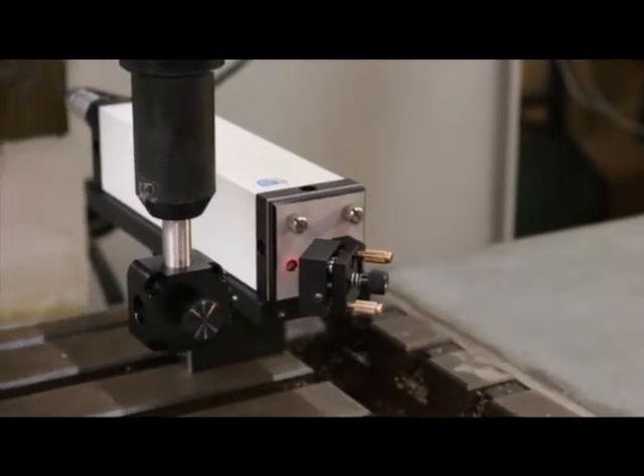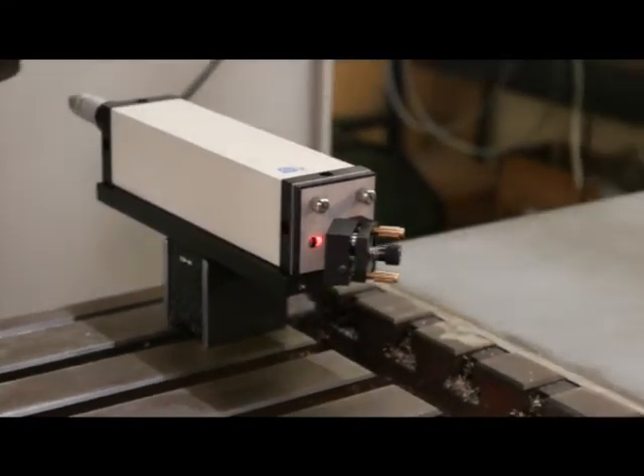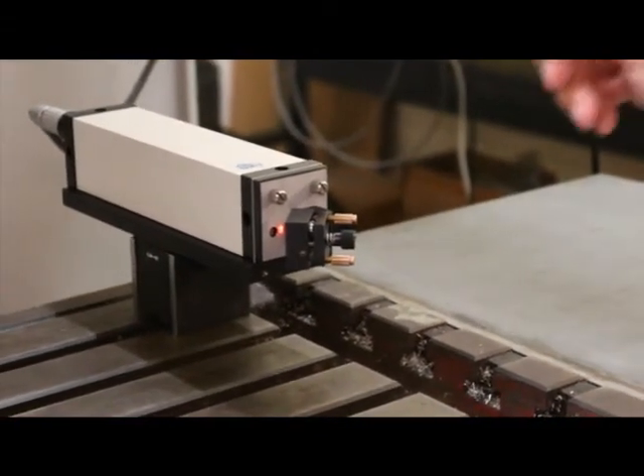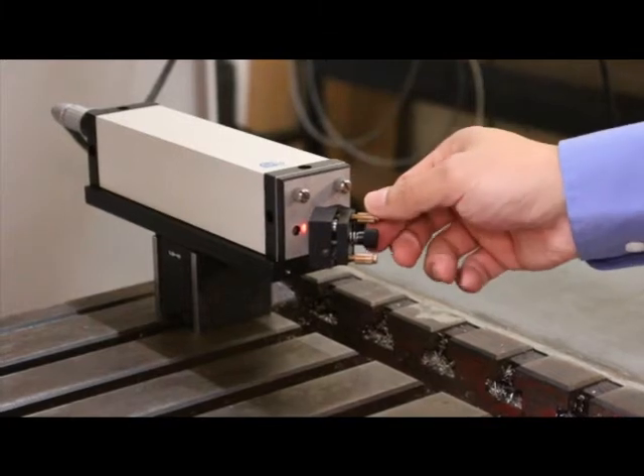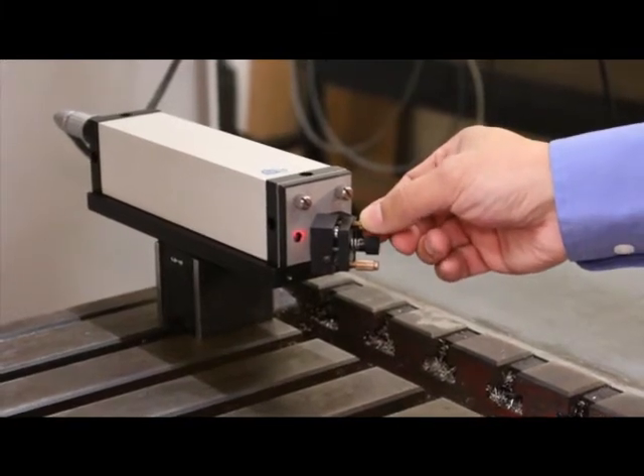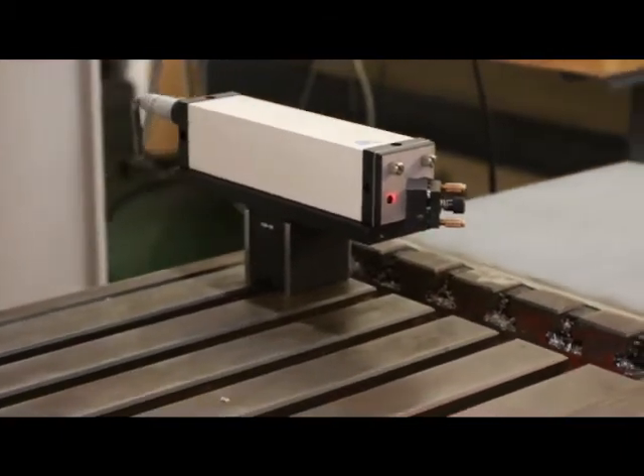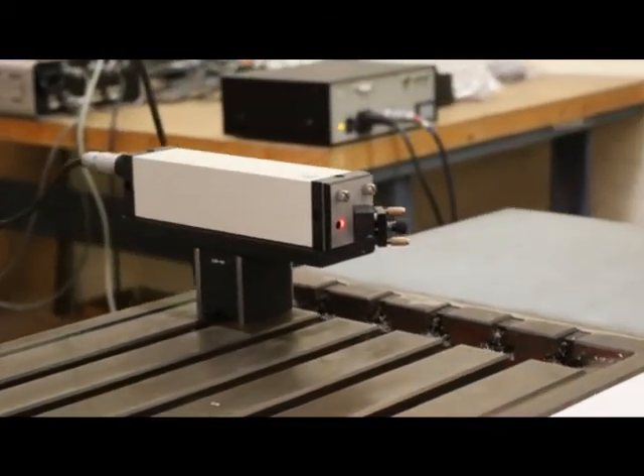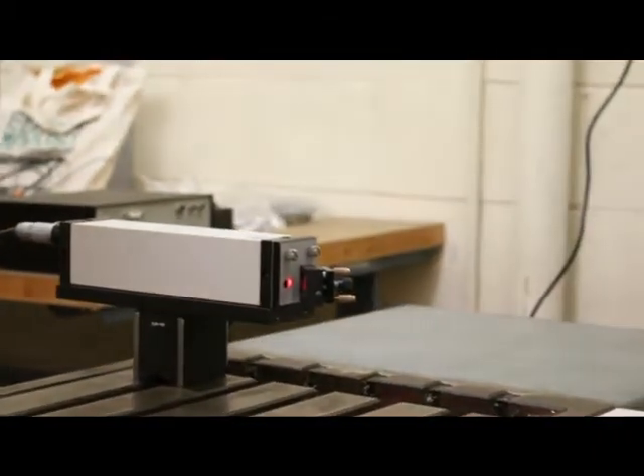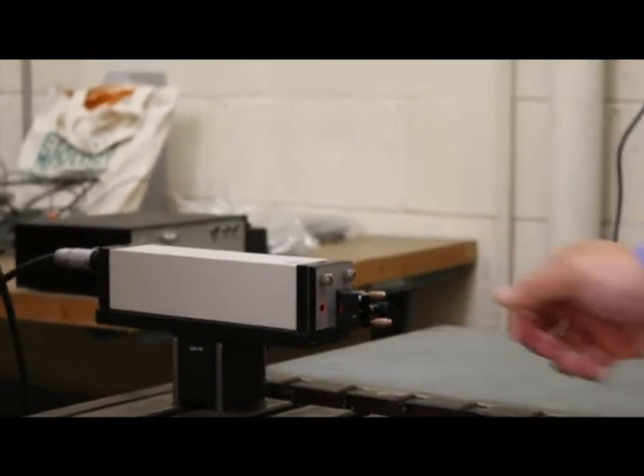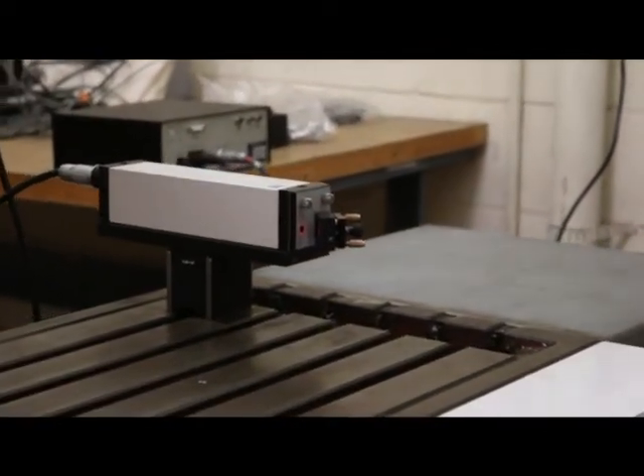Now I am going to move it out on the x-axis. You see the beam is coming out? Now I am going to make all my adjustments using the steering mirror on the laser. Putting the beam back in. Continue to move x out. Putting the beam back in. Moving x back in.